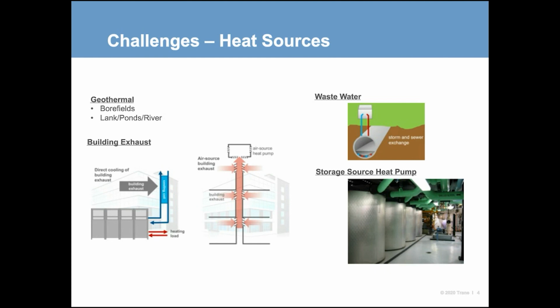All right, so what I have on the screen is just a couple different areas that people are looking at. Geothermal, top left, people have been doing this for a very, very long time, successfully, efficient. The questions become, do you have enough space for it? And do you want to pay for it? The second one, building exhaust. Again, this has been used a lot, but there's been a definite uptick in designs using building exhaust as a source of heat. So the first one there, direct cooling of building exhaust, that's just a hydronic coil in your exhaust airstream, pulling BTUs and using it for heating.